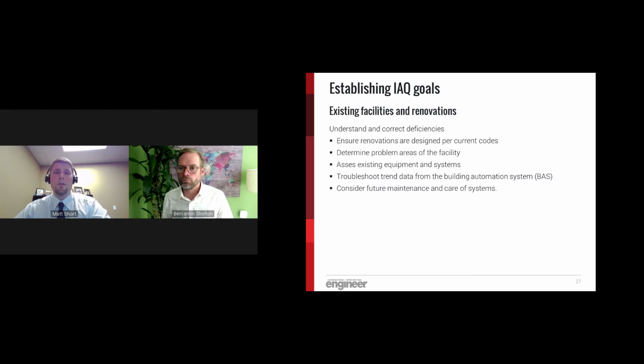Try to determine if there are any problem areas in the building that the owner may have had issues with in the past. Common issues that we see often are hot spots within the building or areas of the facility where relative humidity might be difficult to control. These are often identified with excessive amounts of condensation, things like that.